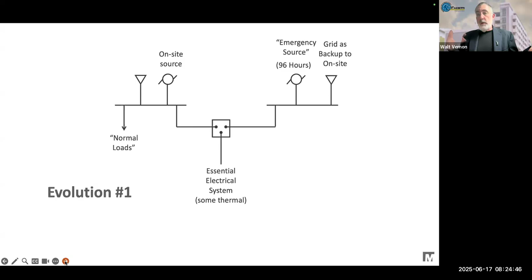Then an era came along where we introduced time of use rates for electricity. Hospitals had these diesel generators just sitting there, and they wanted to run them to eliminate some demand charges from the time of use rates, or sometimes put in a cogen system. The codes evolved and said, okay, you can run your emergency systems all the time for whatever purpose you want—there's a list in NFPA 99, but basically we said you could do that.